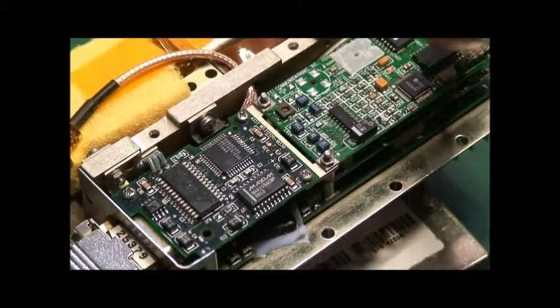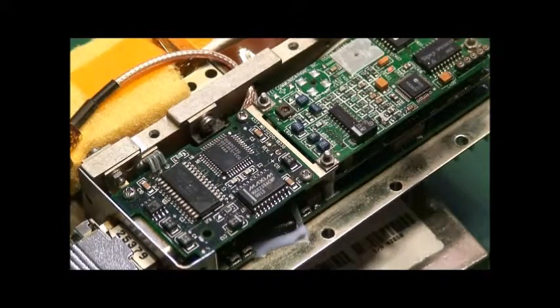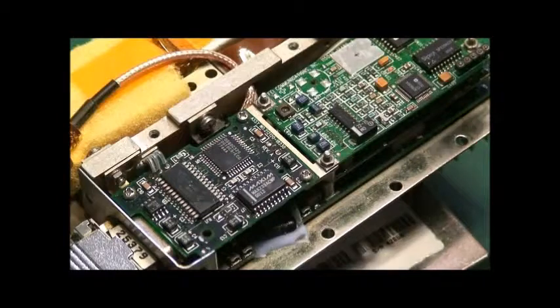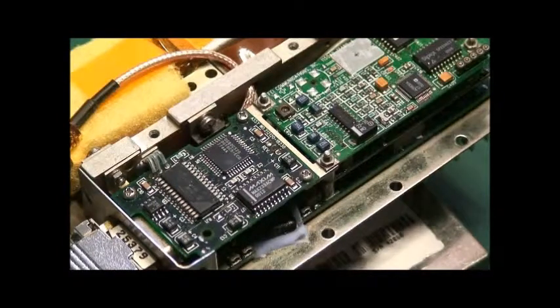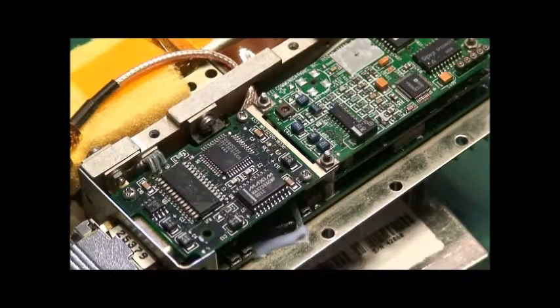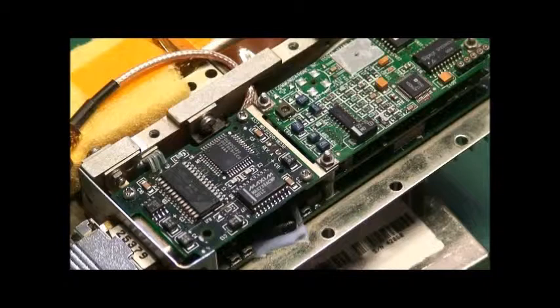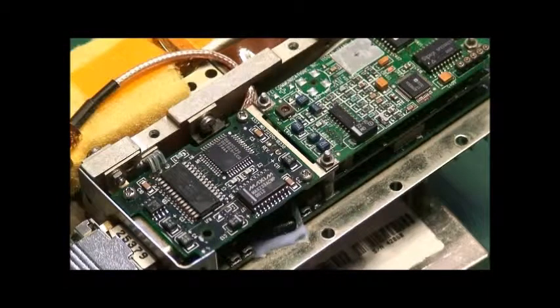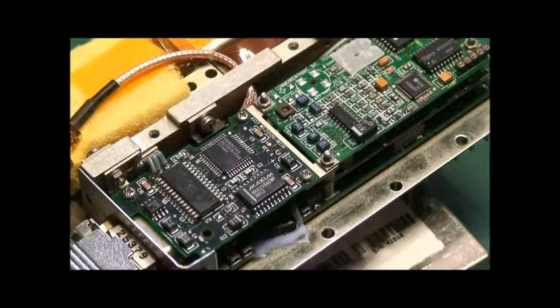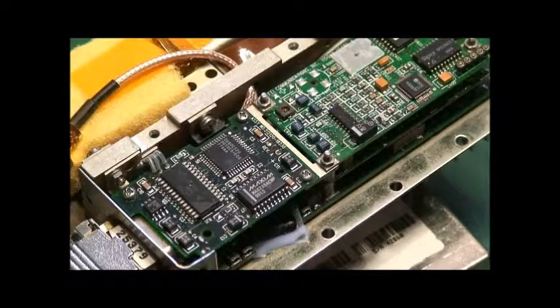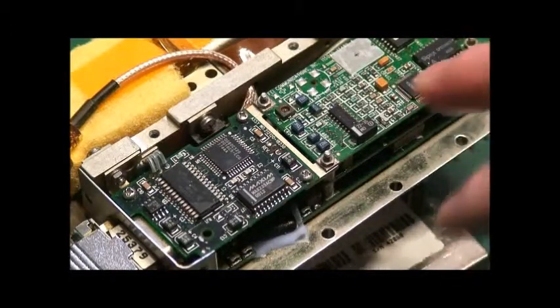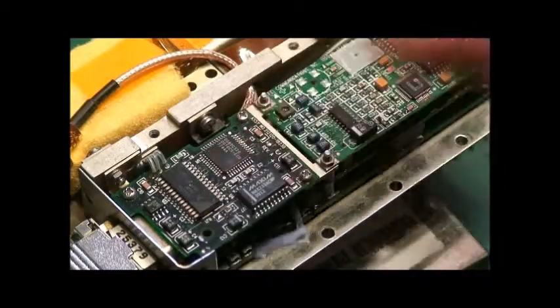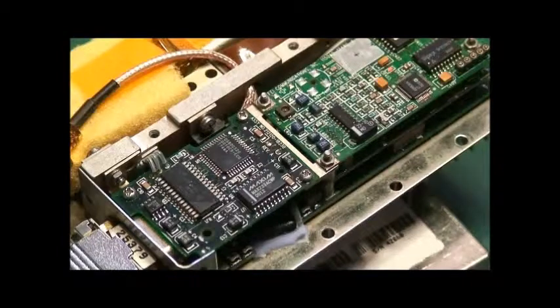This particular unit, the option 58 units, have some additional features on it. You can see there's an additional board here, and there's stacked. There's three stacked boards here, and two here. This has the MAX 232 RS232 interface, so it makes it pretty easy to interface to the unit. And this board has the analog devices AD9830A, which is a programmable divider, and D to A, and that's what makes this unit programmable.